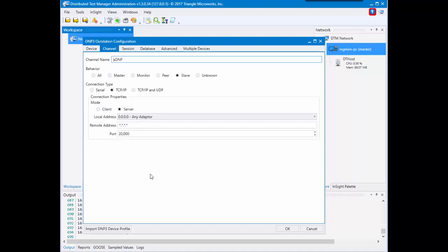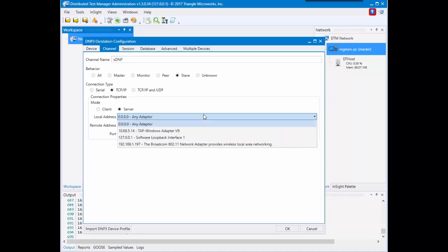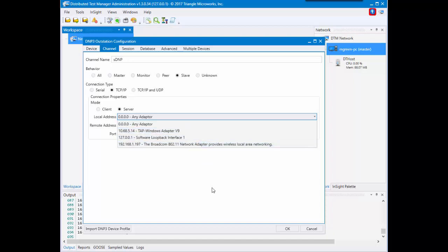In the channel tab, this will affect its behavior and configurations for connections. 0.0.0.0 any adapter is a setting we have for a local address that allows any device or master looking for this specific outstation to connect. If you'd like to make it more specific, you can choose a specific IP address and adapter. It will only communicate on that.